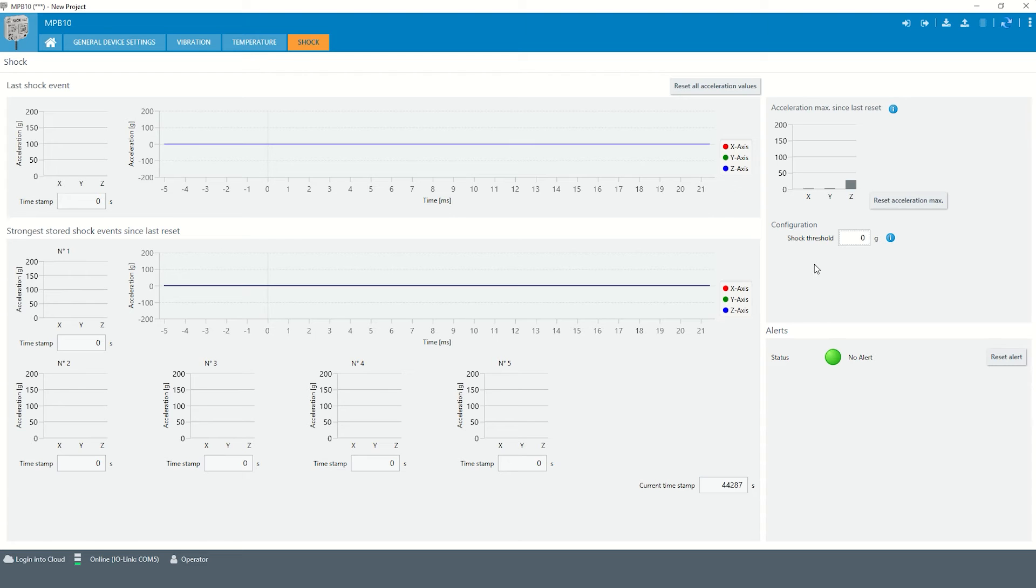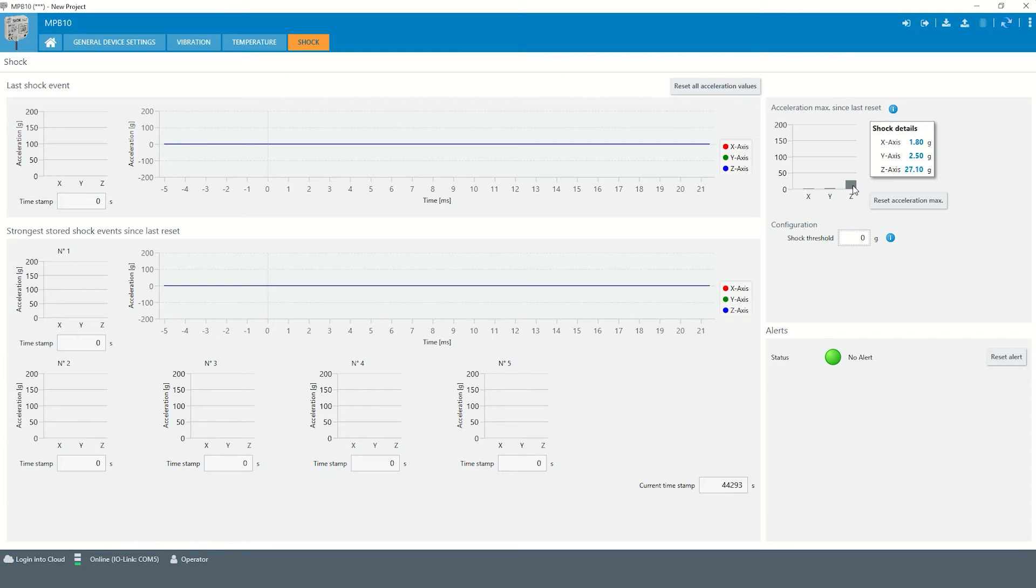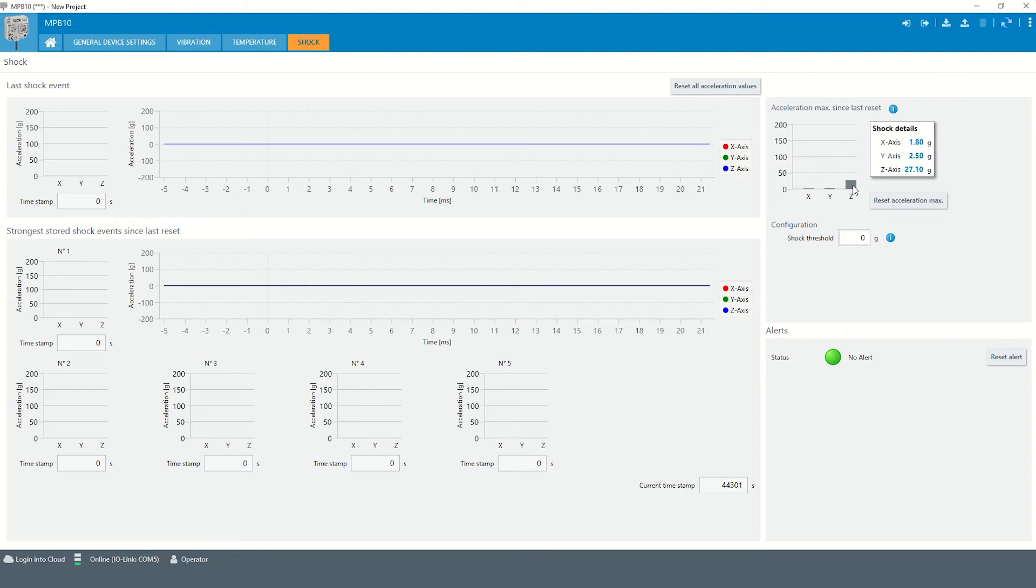The current maximum acceleration can then be read out. With this knowledge of the accelerations occurring during normal operation, a threshold value can be defined a little above.